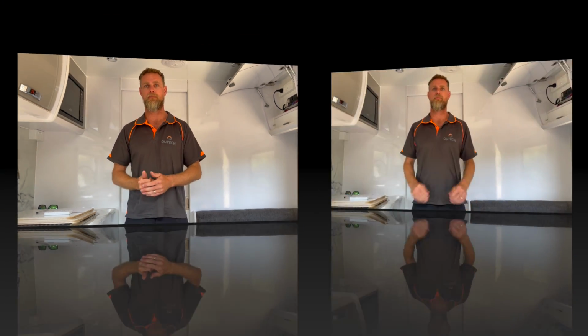Some questions we get asked quite a bit: for example, I've got a caravan with 200 amp hour of lithium and I want to take it from the chassis and bring it inside - do I need to comply? Yes, you do, that's an alteration. Anytime you modify your system to make it different from how it was previously, that's an alteration and needs to comply. So even though you could potentially get away with exactly the same components, that's rewiring the system, and it will need to comply.